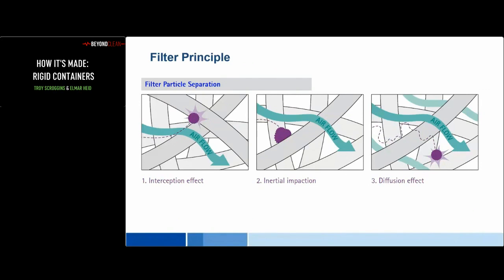Now let's take a closer look at how the filter itself works. Steam and sterilant gases are considerably smaller than microbes and are allowed to pass through the filter. The physical, mechanical, and electrostatic properties of the filter play a role in its effectiveness. Airborne microbes are often bound to particles, such as dust particles. Particles whose diameter is larger than the distance between the fibers generally cannot pass through the filter. In the case of smaller airborne microparticles, there are three effects in particular that cause separation, so they are not allowed to pass through. The first effect is called the interception effect.